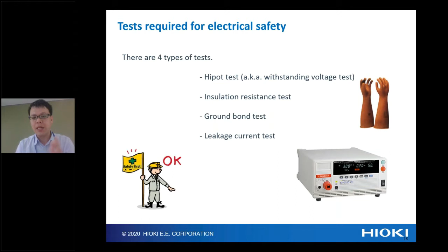What's the purpose of the Hipot test? This is to confirm whether the product has sufficient dielectric strength, meaning insulation strength, against the voltage handled by the electrical product and parts. It is called a destructive test. In particular, it covers user safety, meaning preventing electrical shock, and product safety, preventing fire accidents due to defective insulation, like this picture. Electrical shock and fire are very, very dangerous. That's why, because of this purpose, we have to do the Hipot test.